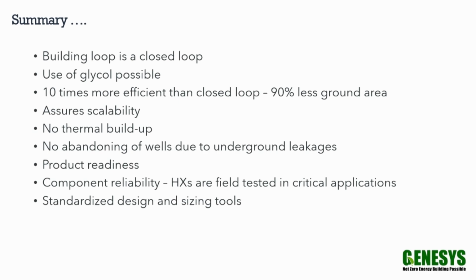An interesting application is you don't need to abandon wells due to leakages. If you stop by our booth, you'll notice there's what we call a pitless adapter that sits on top of this unit. It lets you, in case a pump fails or you need to clean the heat exchanger, pull the whole assembly out of the ground, unscrew the pump, put in a new pump, and put the ground heat exchanger back into the ground. It's fairly simple and easy to do.